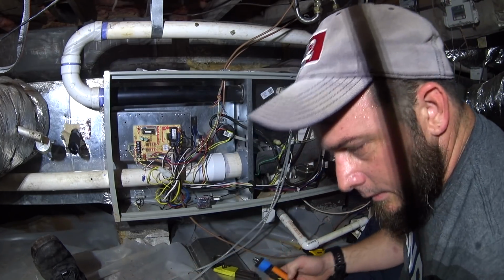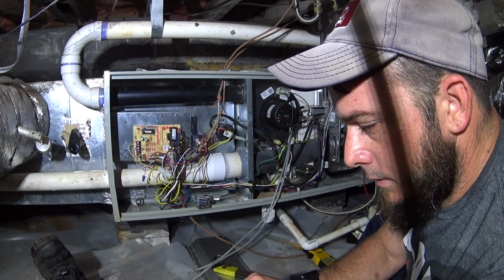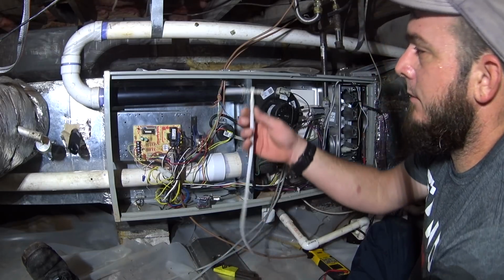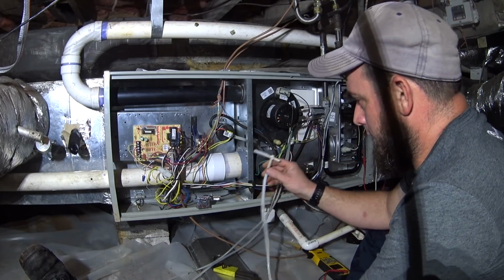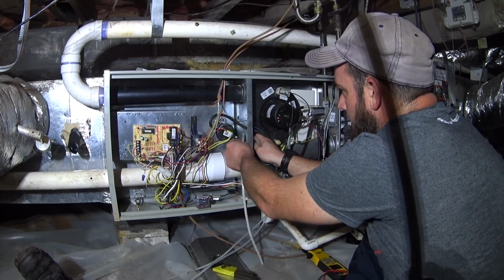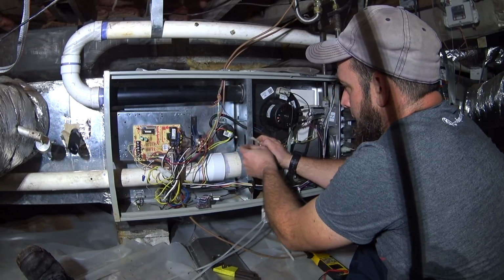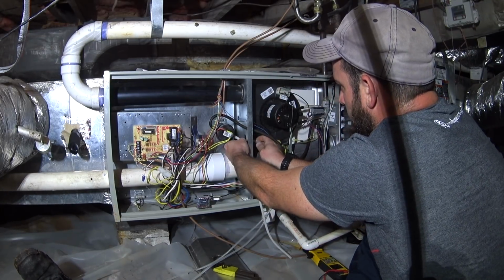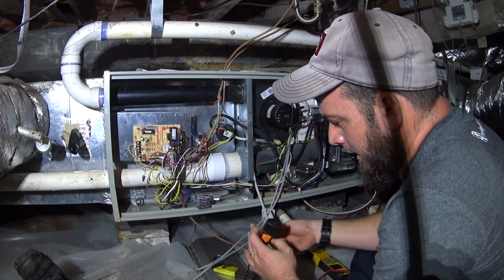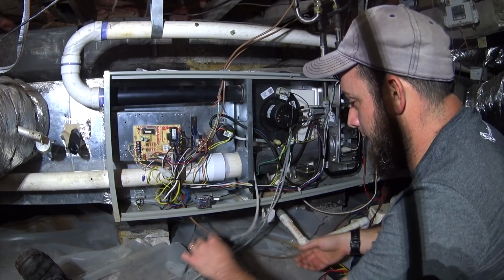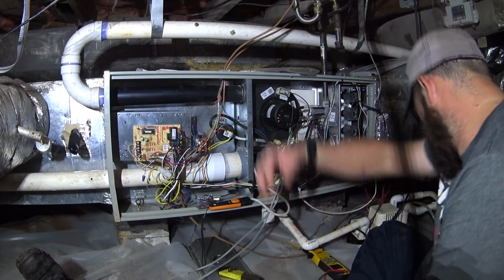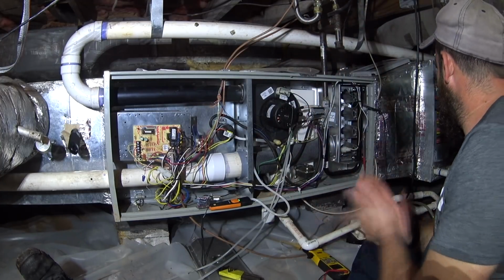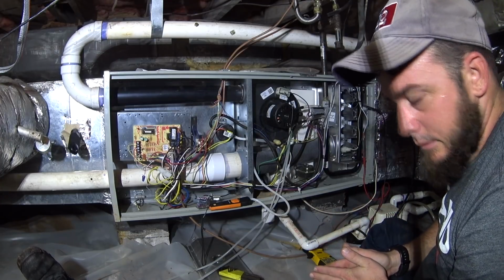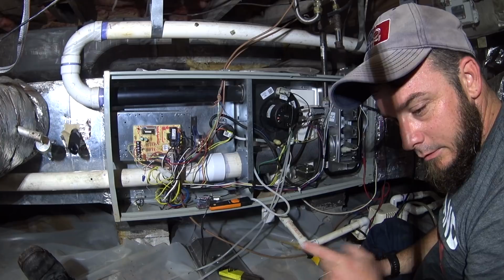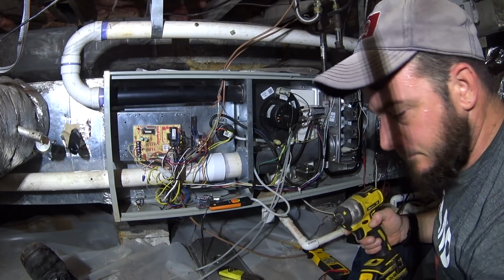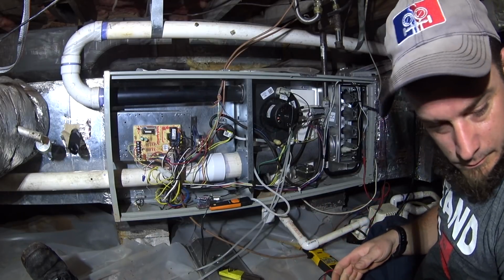So we've got incoming gas pressure, outlet gas pressure, and then I picked up some vacuum tees from the auto parts store for doing tests exactly like this. So I can tee into the inducer motor pressure switch, and since that's going to be pulling a negative pressure, we're putting that on the negative pressure port for the manometer. Alright, so we're going to fire it, get a flame signal, and once we've got a flame signal, we'll close the burner box and fire the system for combustion.